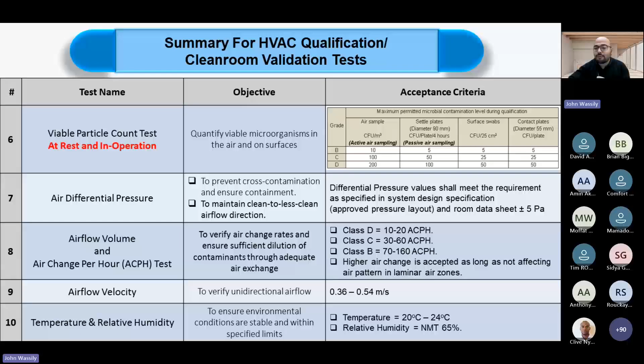Also, part of the HVAC qualification testing is to measure the differential pressure, the airflow volume, the temperature and the relative humidity. And as you can see, for each of those tests, we have acceptance criteria that we shall meet in order to say that, yes, my HVAC system is now fully qualified and could be released for operational use.